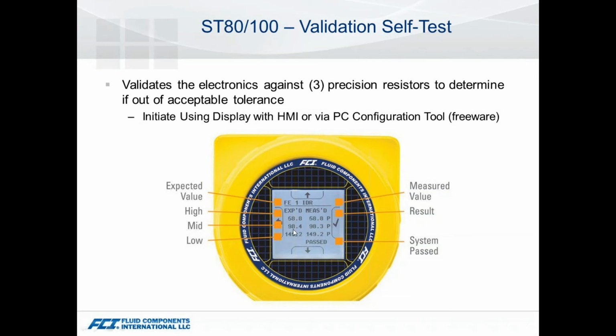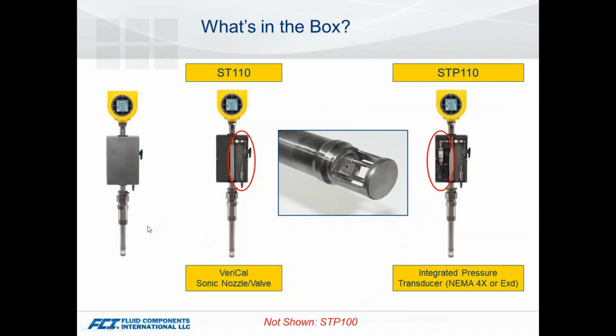Again, what we're doing is swapping in those precision resistors. We're making sure that we're getting the same reading, or very close to the same reading, that we had the day the unit was manufactured. It gives us reassurance that the unit hasn't drifted, and you can see the results. This test takes about a minute overall, 20 seconds for each point. But again, it gives you some confidence that you don't get from a unit without a validation feature.